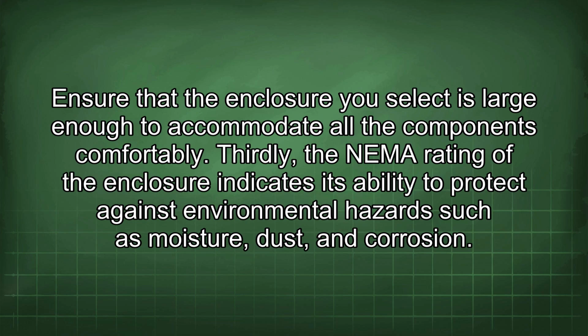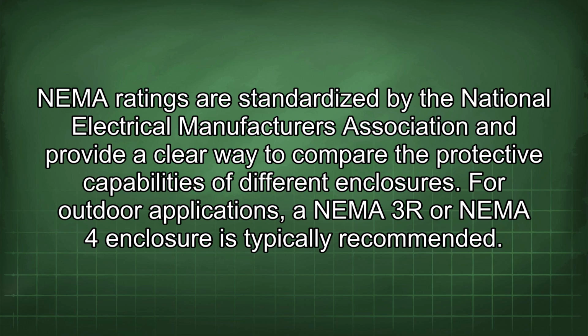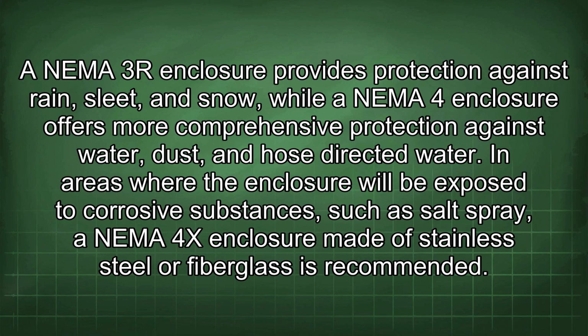Thirdly, the NEMA rating of the enclosure indicates its ability to protect against environmental hazards such as moisture, dust, and corrosion. NEMA ratings are standardized by the National Electrical Manufacturers Association and provide a clear way to compare the protective capabilities of different enclosures. For outdoor applications, a NEMA 3R or NEMA 4 enclosure is typically recommended. A NEMA 3R enclosure provides protection against rain, sleet, and snow, while a NEMA 4 enclosure offers more comprehensive protection against water, dust, and hose-directed water. In areas where the enclosure will be exposed to corrosive substances such as salt spray, a NEMA 4X enclosure made of stainless steel or fiberglass is recommended.